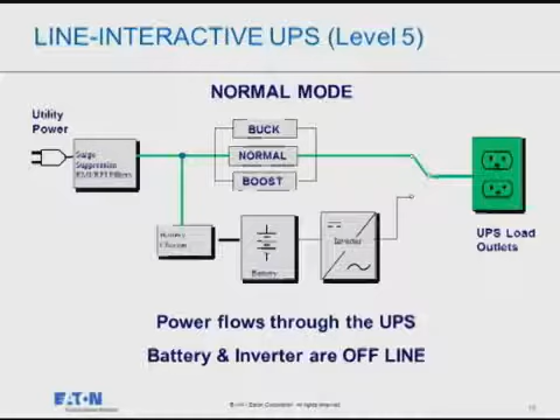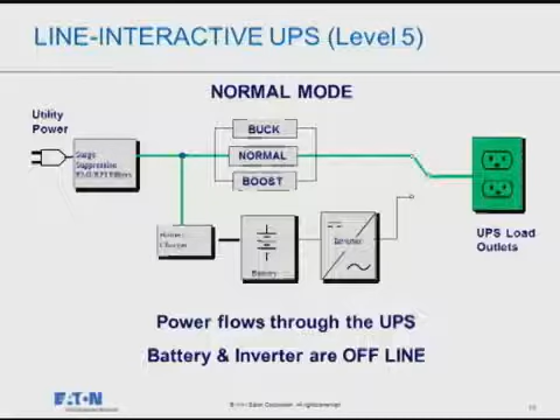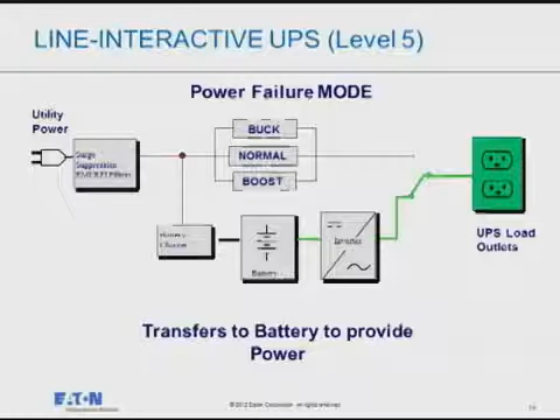So what I've introduced here is very similar to the level 3, or the offline. However, I also have a buck boost circuit in here, and I'll talk about that in a moment. In normal conditions, the UPS is offline, power is flowing through normal mode directly to the load. If I have one of the incidental power problems, a power failure or an extreme sag, it's going to transfer to the battery circuit and supply power to the load. However, where it differs from the level 3 is that it has a buck boost scenario, basically an electronic tap switching transformer with DC or capacitance built in to ride through the switching, where we're going from buck mode to boost mode.